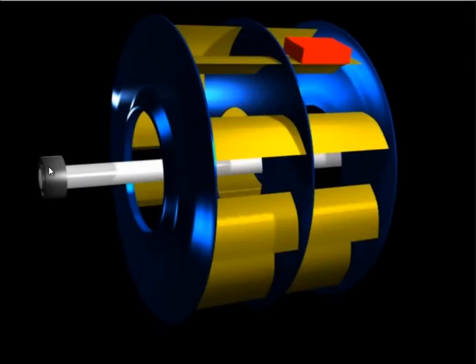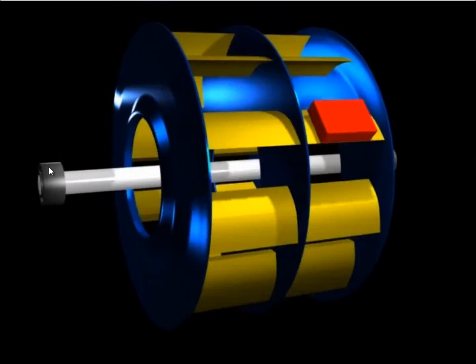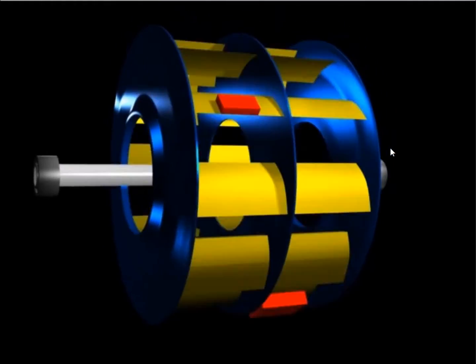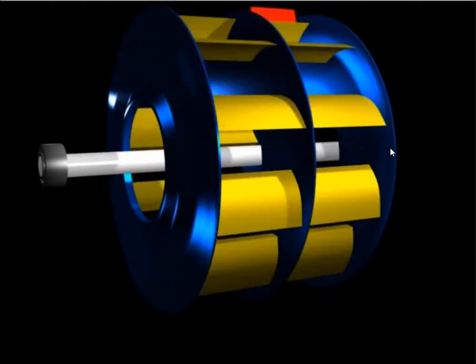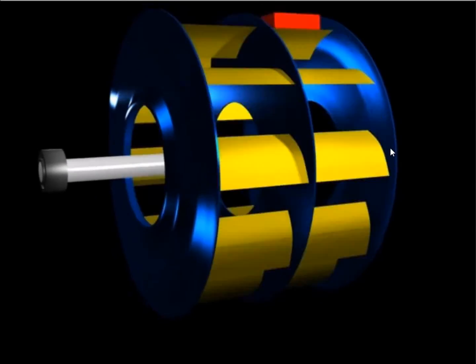The difference is that if we compare the vibration from one end of the rotor to the other, we won't see zero or anywhere close to that, because that would be static. It won't be 180. That would be couple unbalance, but you're rarely going to see that unless it was statically balanced, leaving you with just couple unbalance.